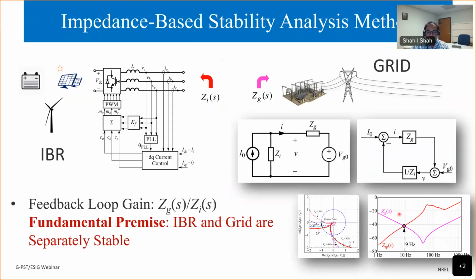not. So the fundamental premise behind this method is that the IBR is stable in isolation, when it is connected to a strong grid or ideal grid, and the grid is stable without the IBR. And that is the fundamental premise. This is a reasonable assumption to make, that an IBR would operate stably when it is connected to a strong grid. So the question we ask is, what happens when we connect them together? When the IBR is connected to the grid, whether they remain stable or not. So that is the fundamental premise, that the IBR and grid are separately stable. What happens when we connect them with each other?